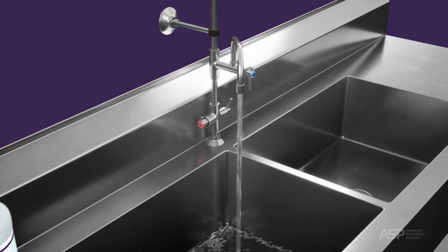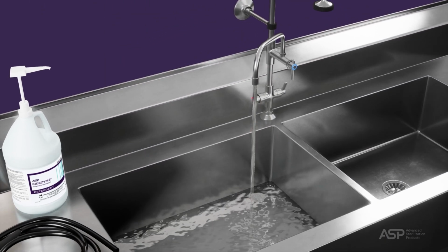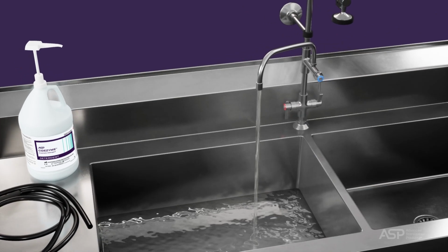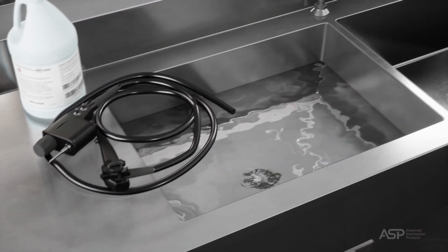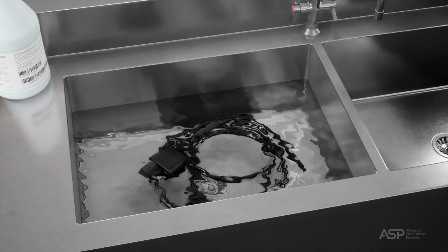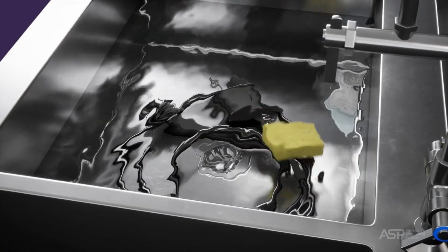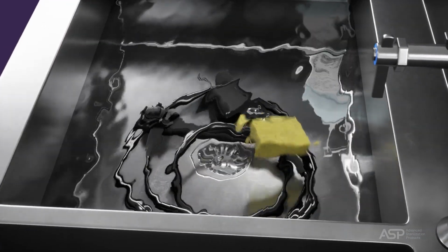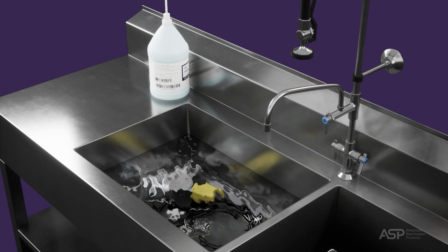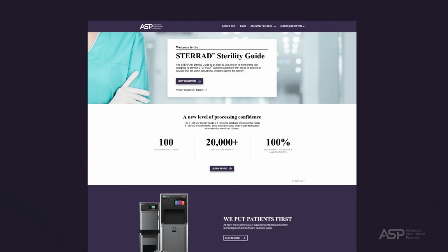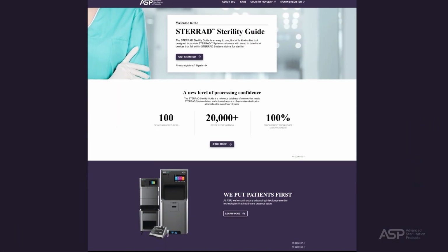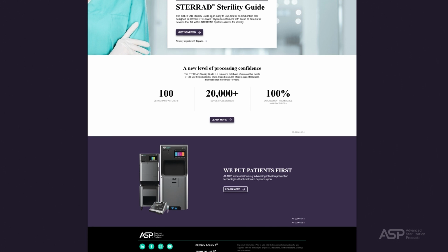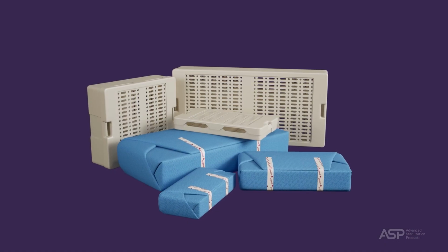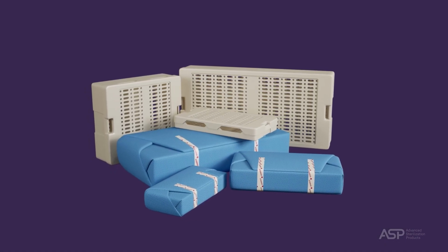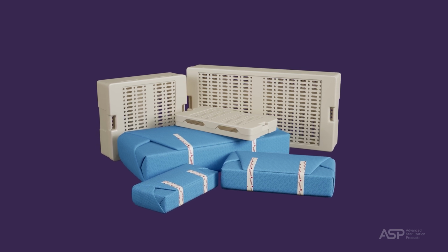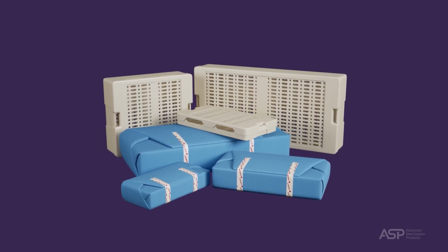Let's talk about preparing a load and reprocessing in the STERRAD 100NX Sterilizer with ALLClear technology. Prior to reprocessing, all individual devices should be cleaned, rinsed, and thoroughly dried according to the manufacturer's instructions for use. Check the manufacturer's instructions for use or the STERRAD Sterility Guide to determine which cycle the device has been validated for.